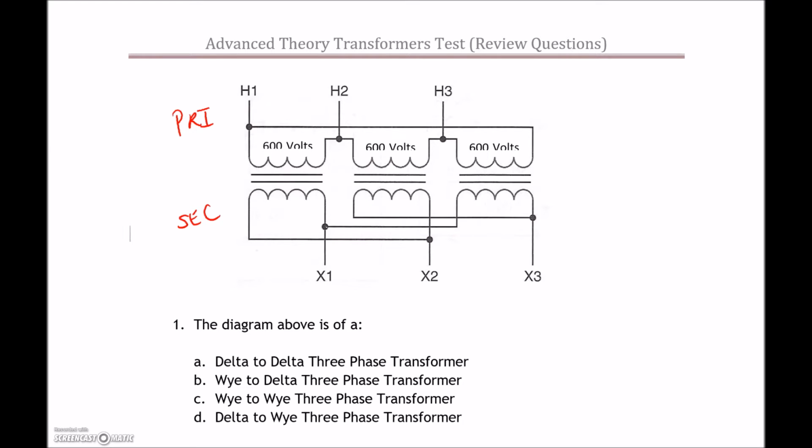So let's see. We've got this connection right here for this winding, and it seems to go to H1. I'm going to label that guy A, because that's our A phase. Then we've got B. Then we've got C. So that's going to help because I gave you that mnemonic to remember. Because we know that for a Y, everything's tied together at that star point, which it doesn't seem to be the case on this guy. Not everything is brought together. So it must be a delta.